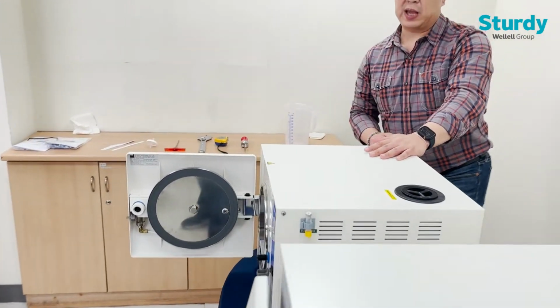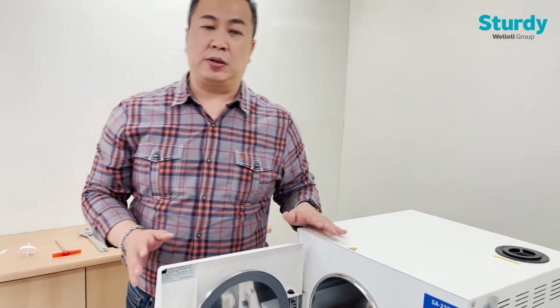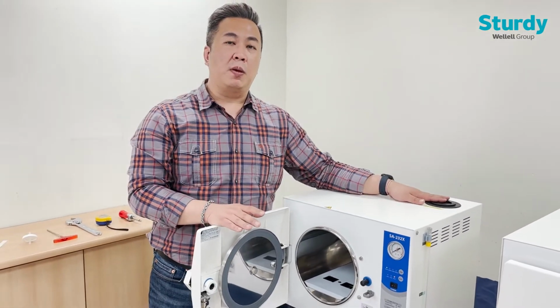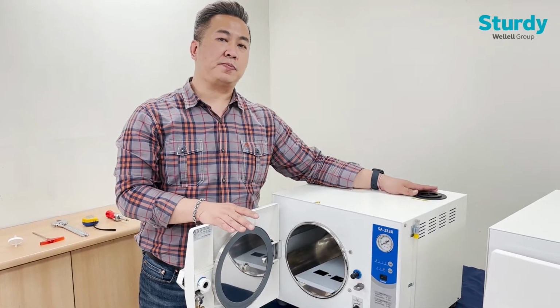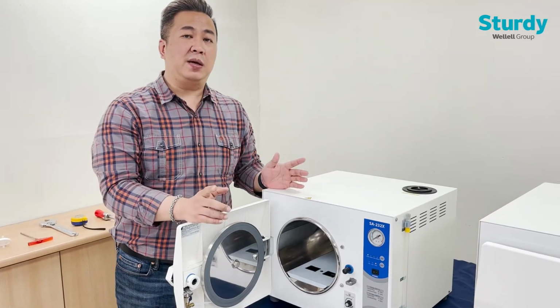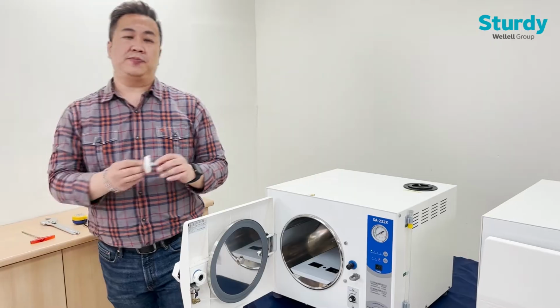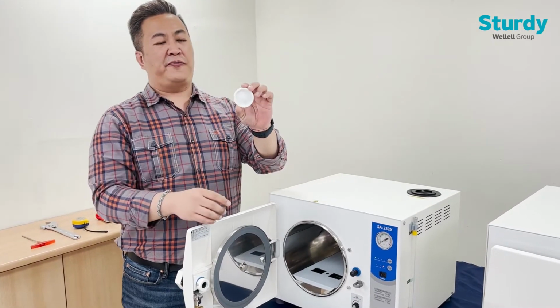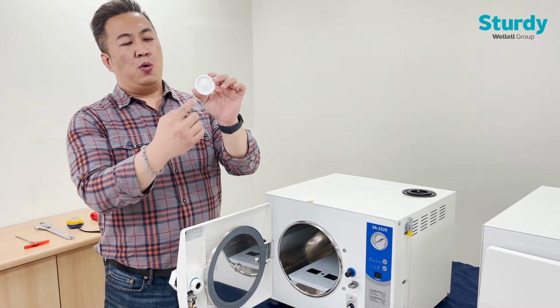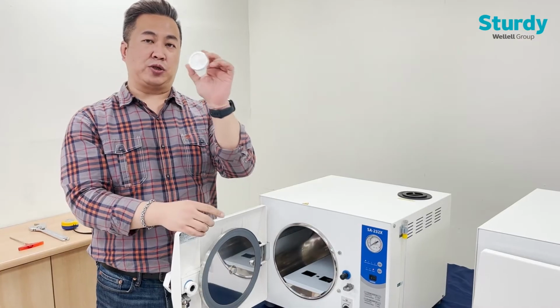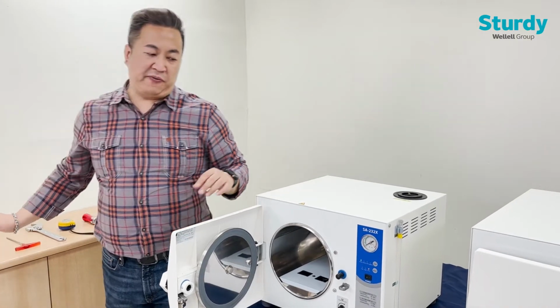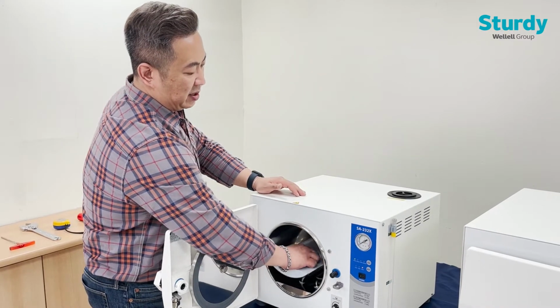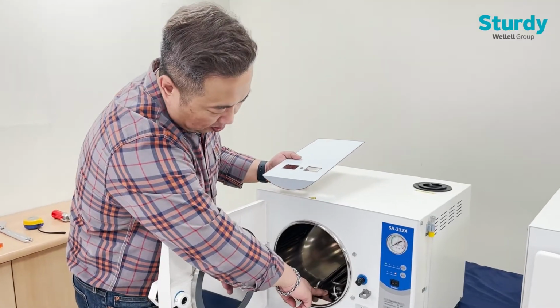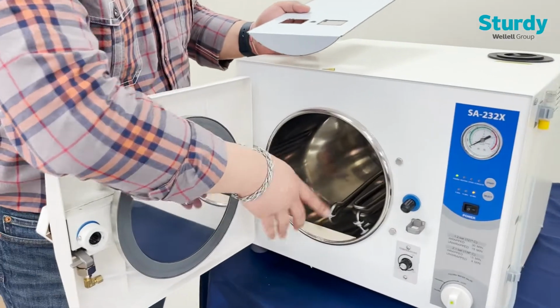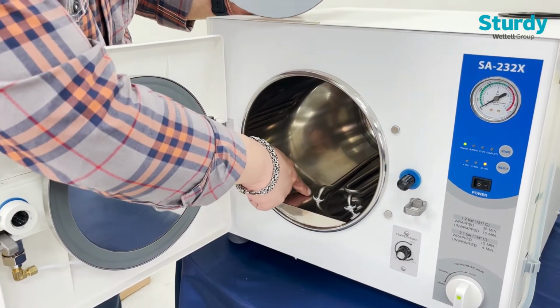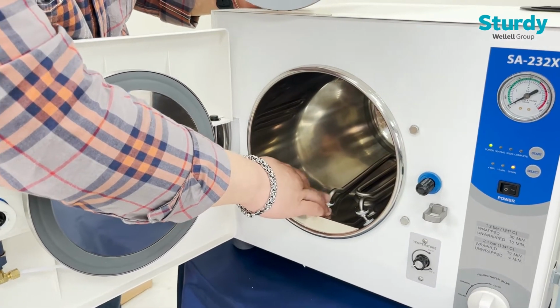For the monthly maintenance, besides all that has just been explained, we also need to replace the RO water and check that the water quality is at 100%. We also need to change the air filter, which is located inside the machine. How do we identify that the air filter needs to be replaced? Once it has turned all black, that means the filter has to be changed. Also, we need to verify whether the water level sensor, if available inside the chamber, needs to be cleaned or replaced. Also, just visually check that the heating rod is at 100% quality.